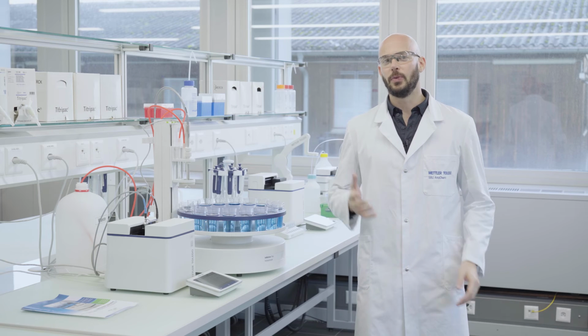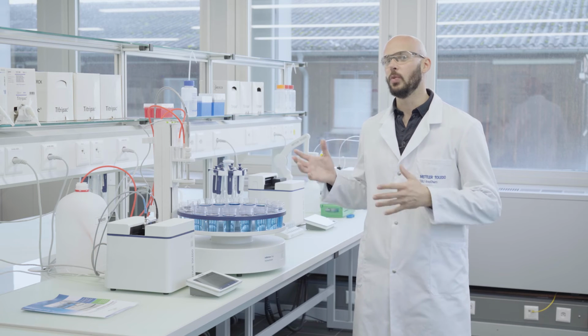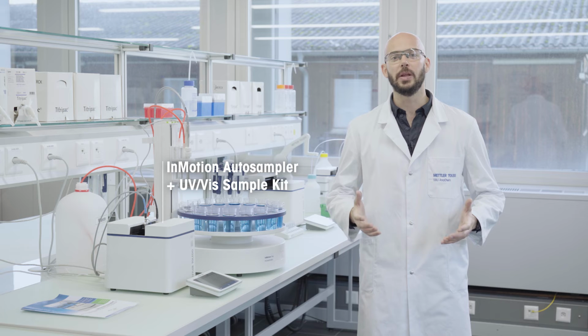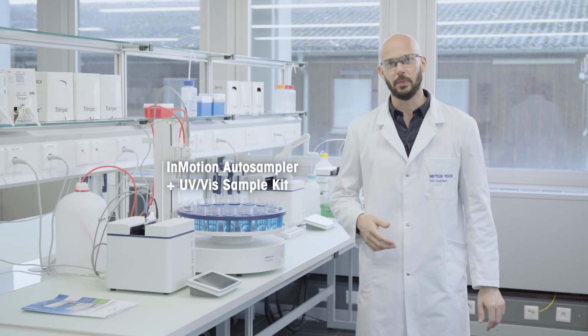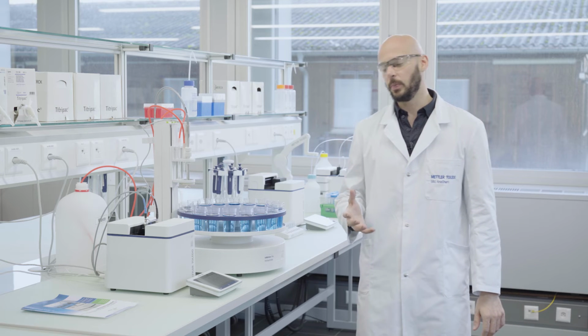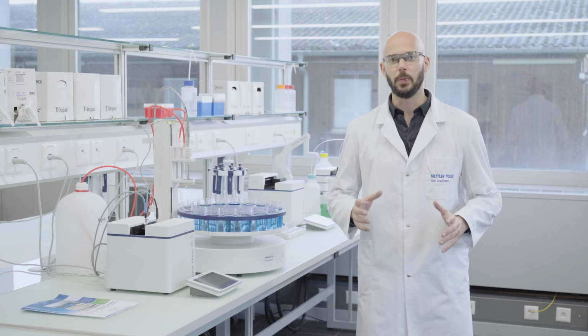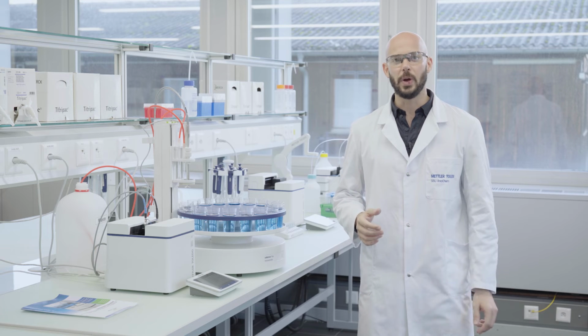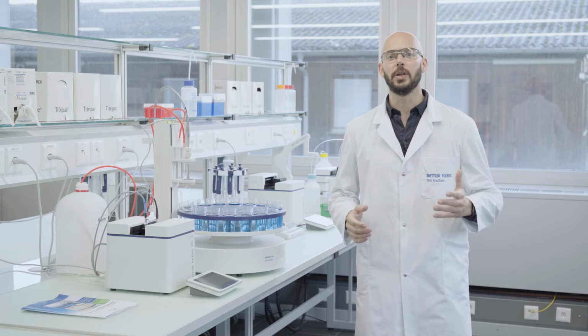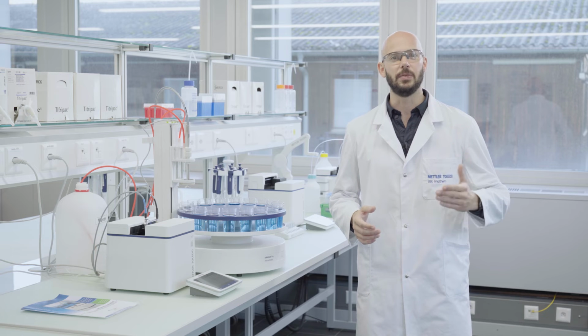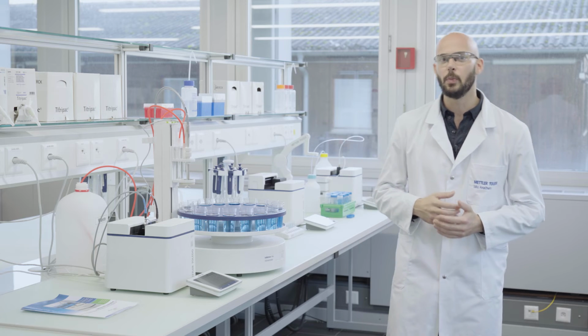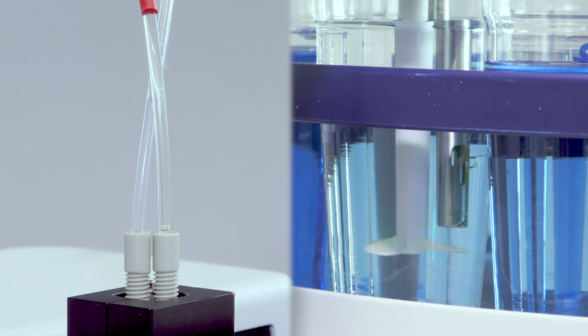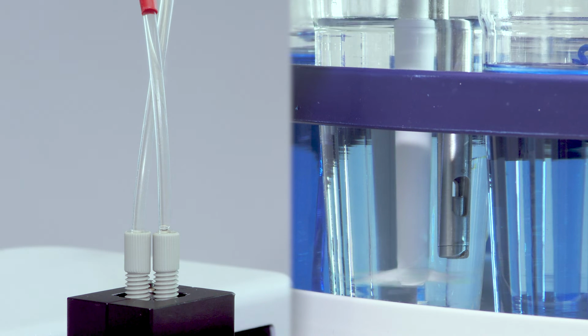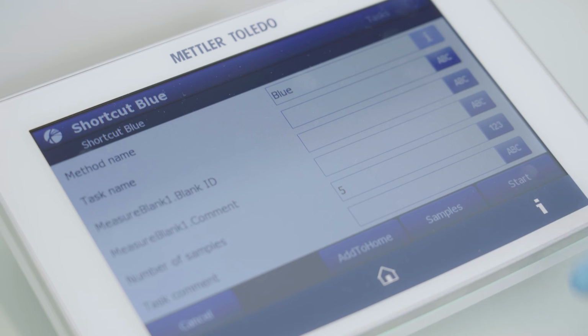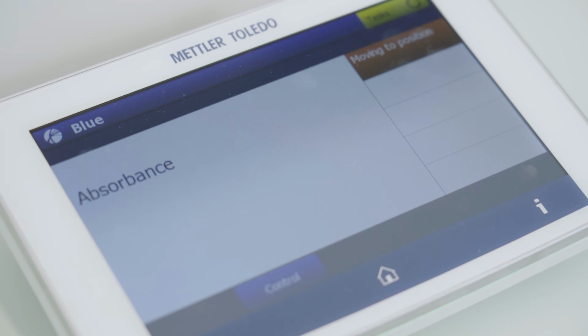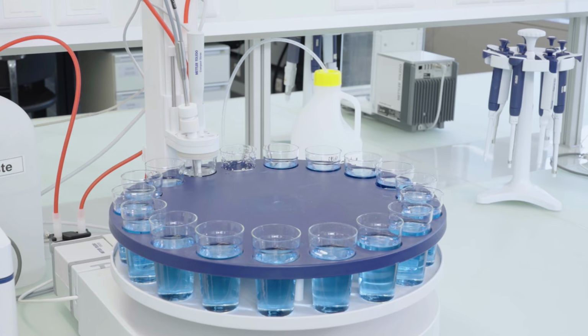For the automation of larger sample series, we offer the InMotion autosamplers, which can automate the measurement of up to 303 samples. They come in 3 different base versions, the Flex, the Pro, and the Max, and each can be combined with different rack kits to accommodate different beaker sizes and different beaker numbers. The InMotion autosamplers can be combined with 2 sampling techniques, flow cells and immersion probes, by selecting the right sample kit. Here we see an InMotion system equipped with an immersion probe.